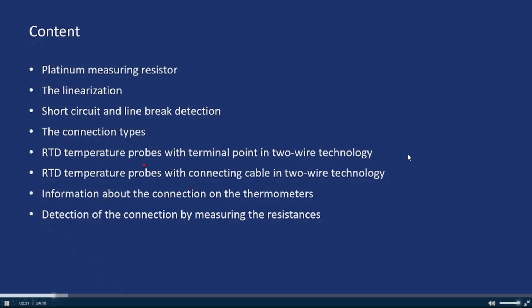Then I want to show you that it's not so hard if you have an RTD temperature probe with a terminal point in 2-wire technology. Normally when you work with 2-wire technology you have an offset, but if you have a terminal point and you need to work with your own connection cable, then it's not such a big offset. On the other hand, if you have an RTD temperature probe with a connection cable in 2-wire technology, this is not so nice, because here the offset will normally be higher if you work with a PT100.